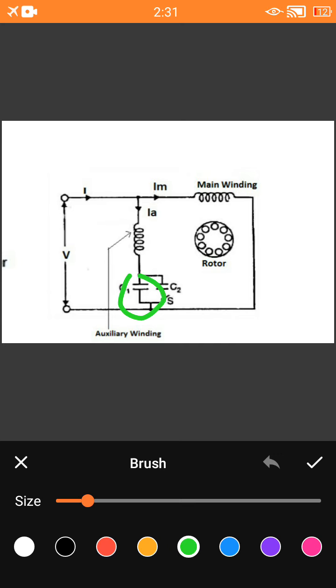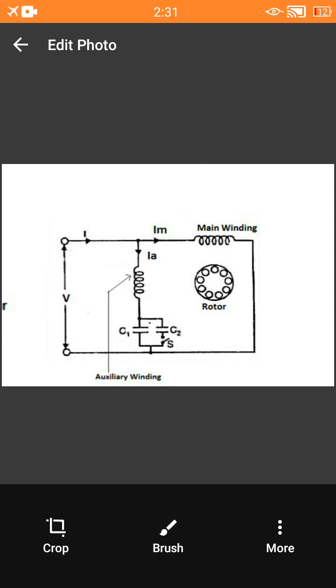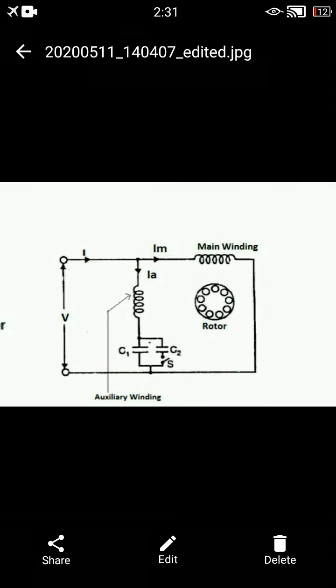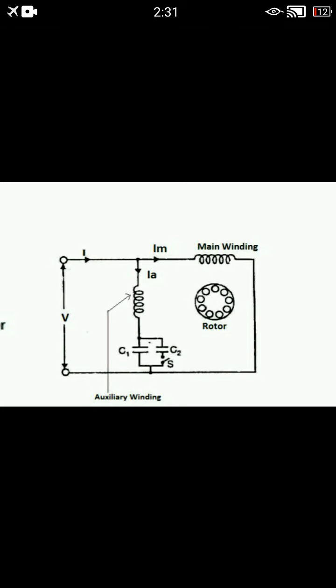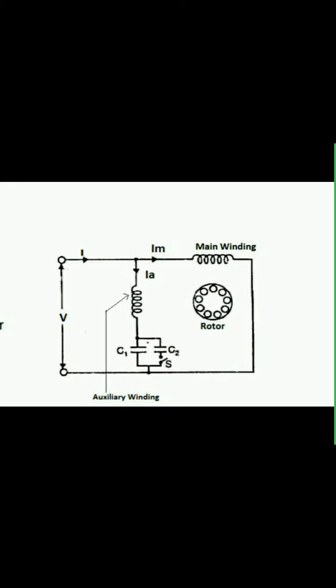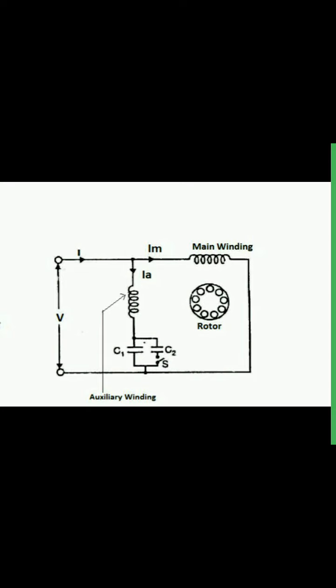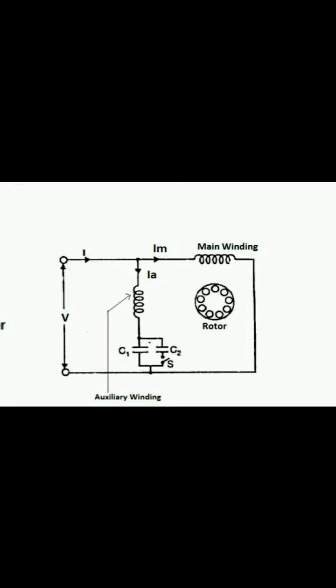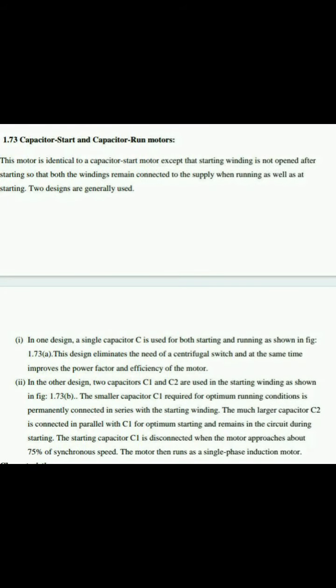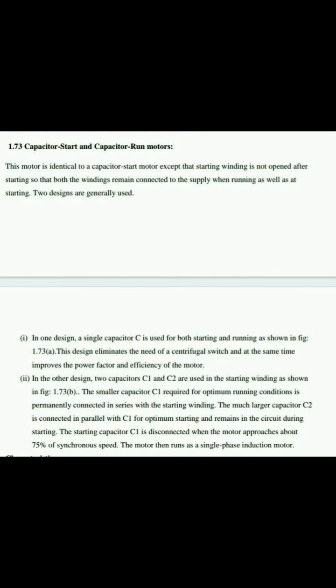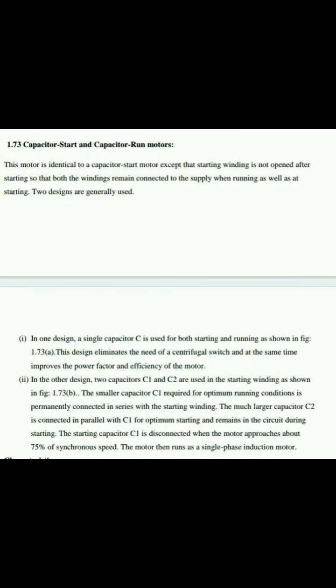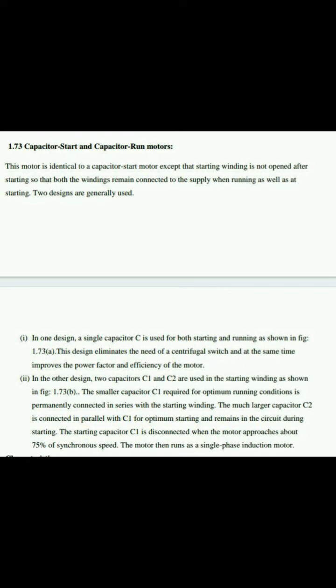That is why this motor is called the capacitor start and capacitor run induction motor. According to its construction, the stator is made up of silicon steel and the rotor is a squirrel cage rotor made up of copper bars, short-circuited with end rings. This motor is identical to the capacitor start motor except that the starting winding is not opened after starting, so both windings remain connected to the supply during running as well as starting.